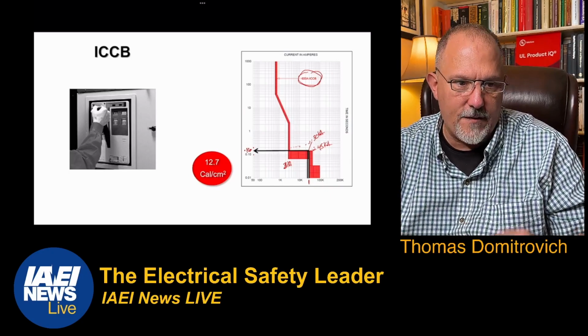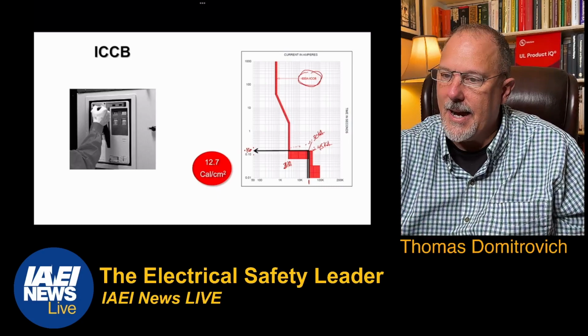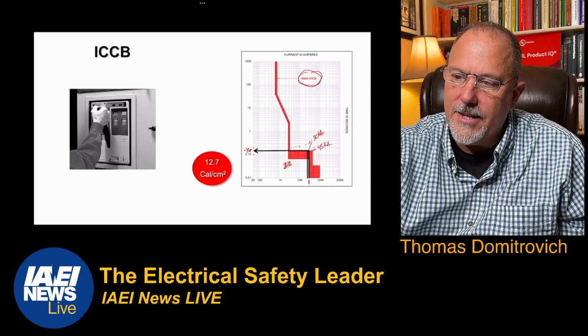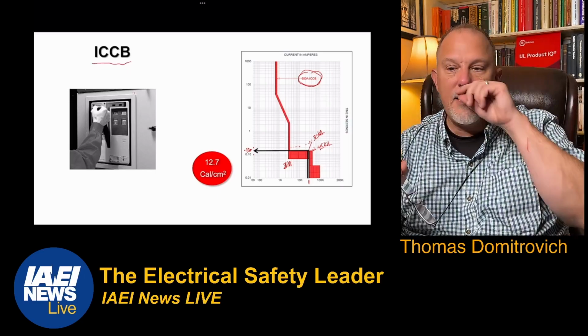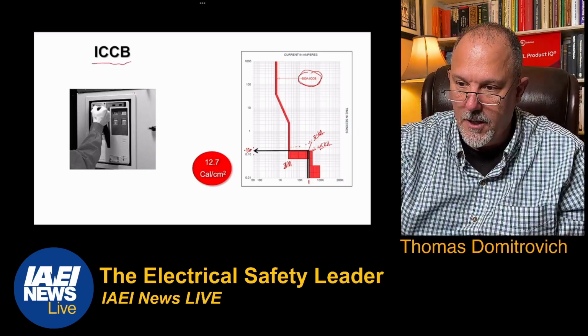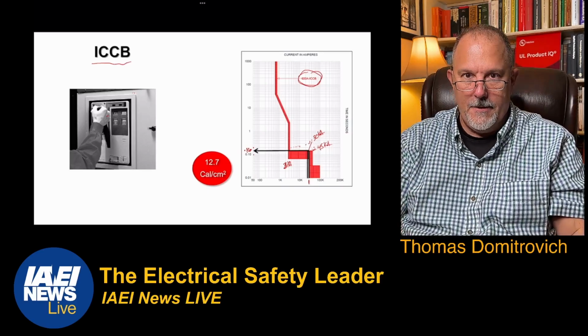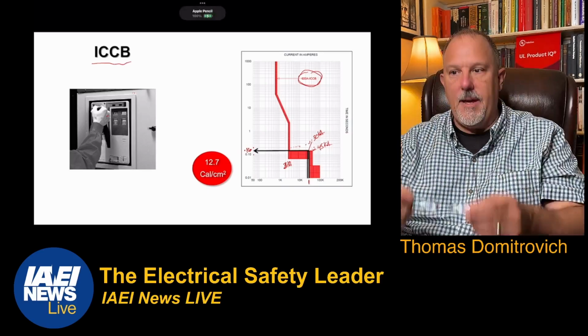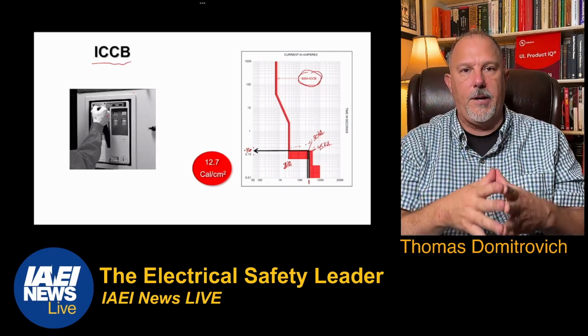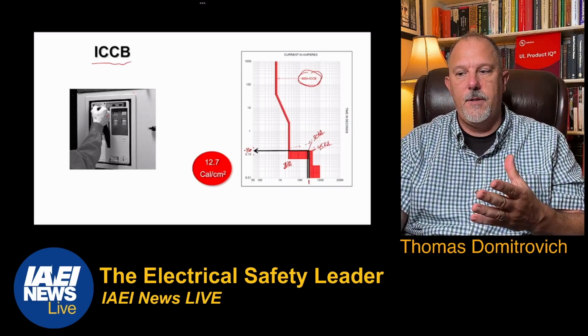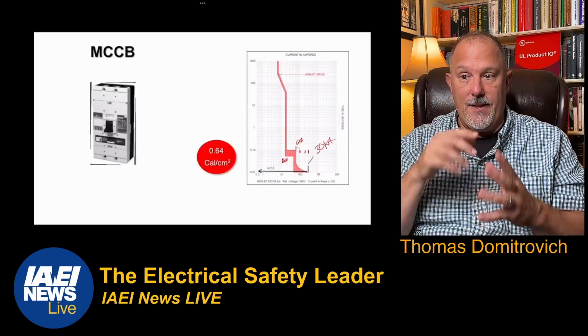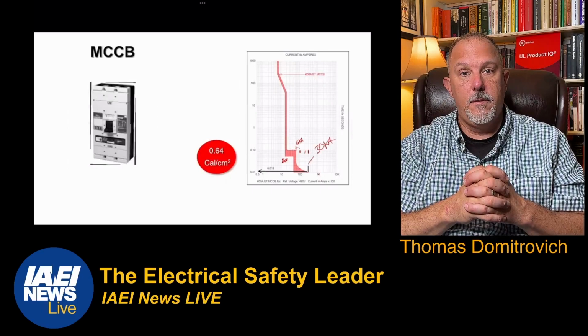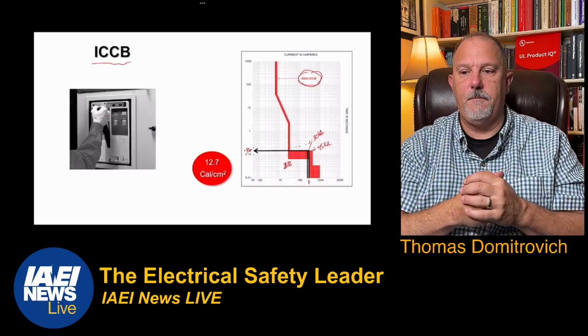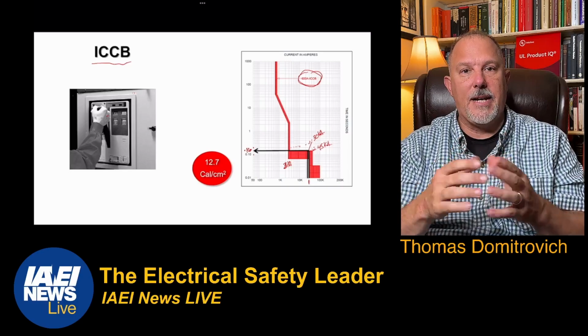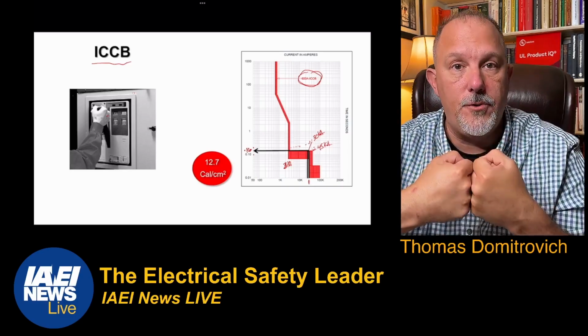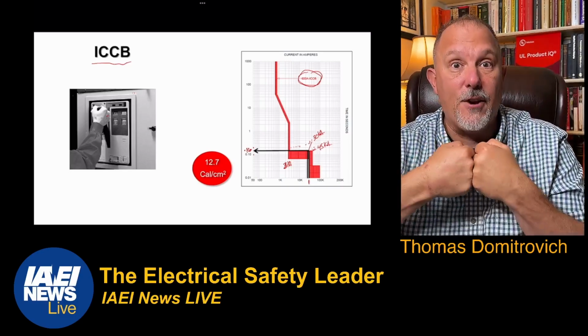The only thing I did, everything else exactly the same, is that I put in an insulated case circuit breaker. What's the difference between the breakers? Look how big that is in comparison to his hand. Why would I make an insulated case breaker that's 600 amps much bigger than that device? Why do I have all the beef? Because I need those contacts to stay closed longer at higher fault currents.